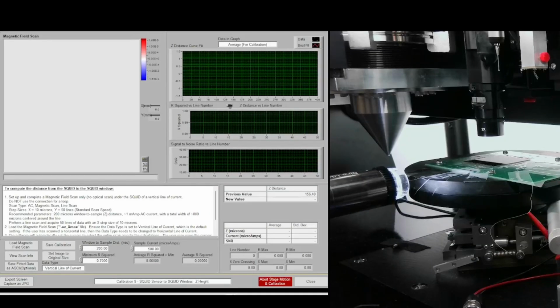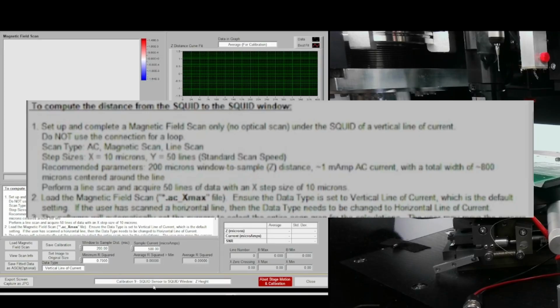We've now moved into Calibration 9, aligning the SQUID sensor to the SQUID window Z height. For this calibration, we're going to run a magnetic-only scan, with no optical data. You'll find the scan requirements in the info box at the lower left of the interface. It's a line scan with a step size of 10 microns in X and 50 microns in Y, a 200 micron distance from the sensor to the sample, and a current of 1 milliampere AC.